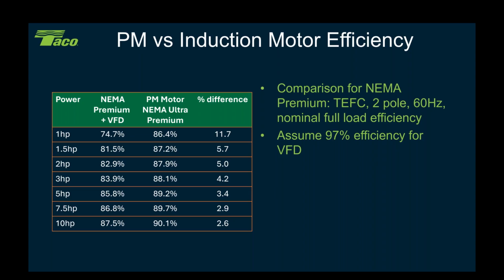I should say, let me rephrase that. The ultra premium is the permanent magnet. The NEMA Premium is the conventional induction. It's the high performance induction motors. But you'll notice that in the small sizes, that ultra premium motor, the permanent magnet motor, is more efficient. The problem is, as you get bigger and bigger, the gains in efficiency start to fall off, okay? And once you get above 10 horsepower, it's about 2.5 to 3% more efficient in an ultra premium motor than it is a conventional induction motor. So the efficiency gains aren't as dramatic the bigger you get. It's not to say that they're not good, and it's not to say that they're not better, but understand that the efficiency gains aren't as dramatic the bigger you get.